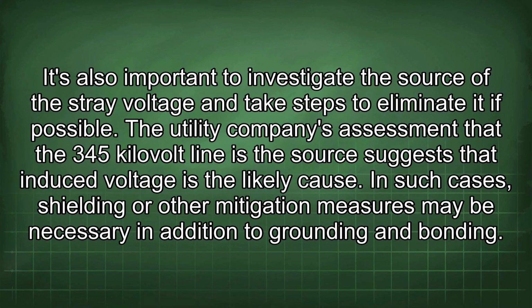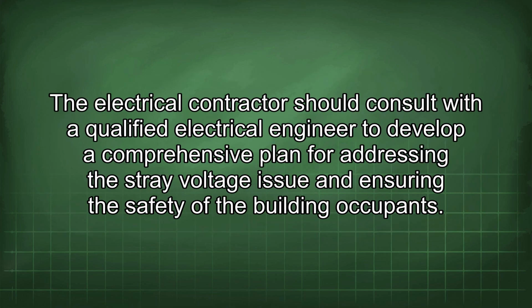The utility company's assessment that the 345 kV line is the source suggests that induced voltage is the likely cause. In such cases, shielding or other mitigation measures may be necessary in addition to grounding and bonding. The electrical contractor should consult with a qualified electrical engineer to develop a comprehensive plan for addressing the stray voltage issue and ensuring the safety of the building occupants.